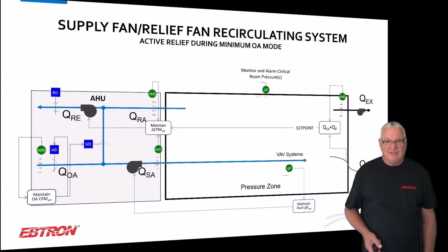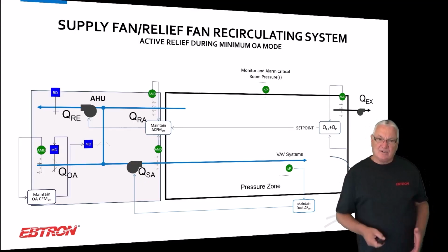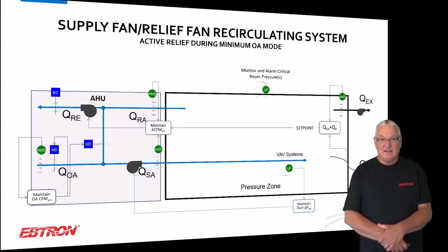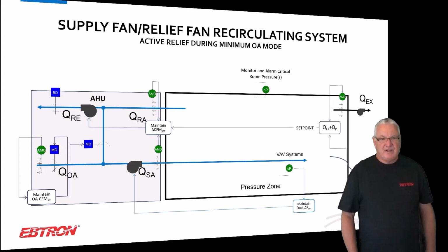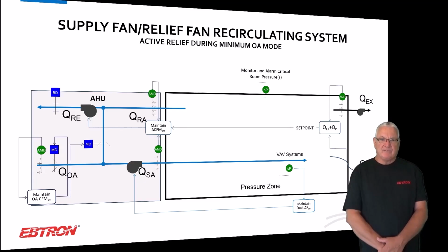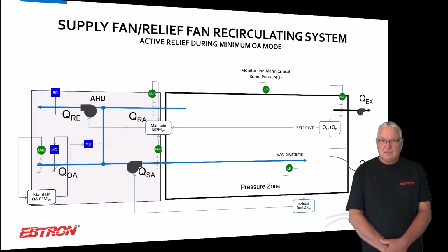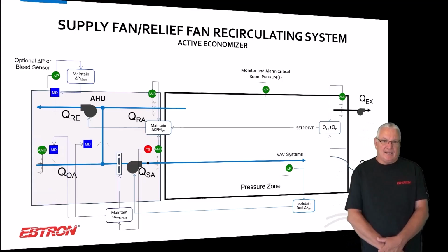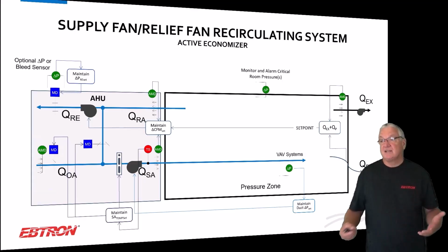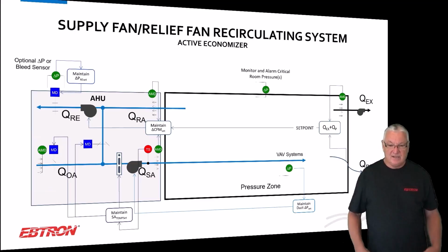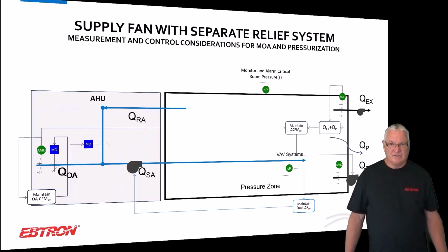Okay, when we're actively relieving air, it's really the same thing. It's identical to what we were doing with the supply return air fan. The difference is we're just controlling the relief air fan. And I've had people say, well, how does that work? What keeps me from bringing in outside air and just relieving it? Well, what keeps you from doing that is you're controlling the supply and the return air flow rates. So as long as those measurements are working properly, you're not going to be doing that. It's not going to happen. And again, economizer, it's really no different. So for us, we run kind of the same strategy: supply return, supply relief fan. The only exception being supply return fan when there's no relief.